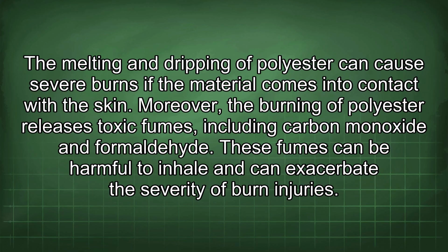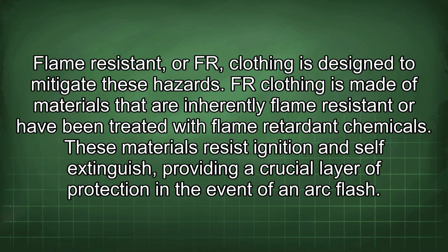Moreover, the burning of polyester releases toxic fumes, including carbon monoxide and formaldehyde. These fumes can be harmful to inhale and can exacerbate the severity of burn injuries. Flame-resistant or FR clothing is designed to mitigate these hazards. FR clothing is made of materials that are inherently flame-resistant or have been treated with flame-retardant chemicals. These materials resist ignition and self-extinguish, providing a crucial layer of protection in the event of an arc flash.